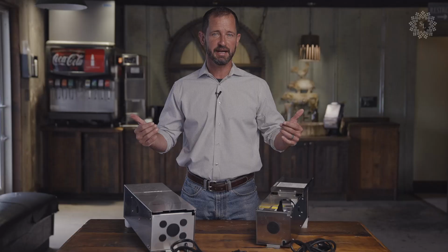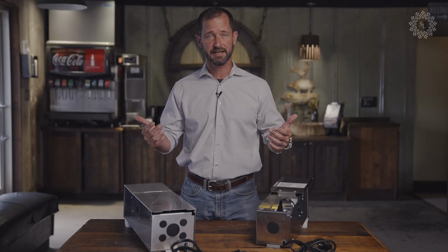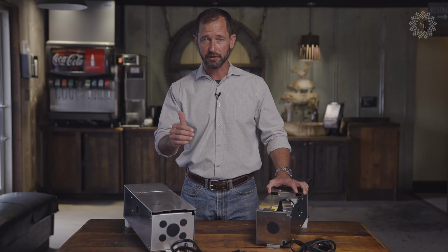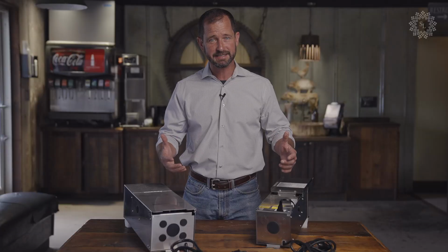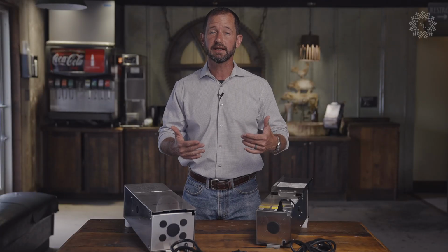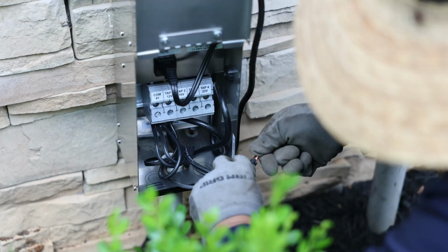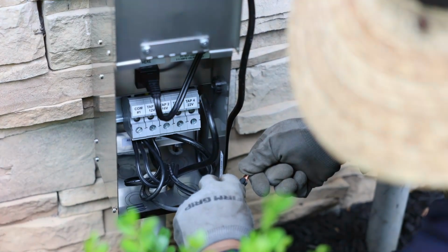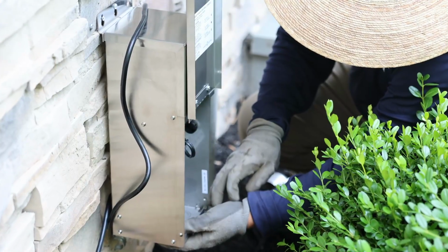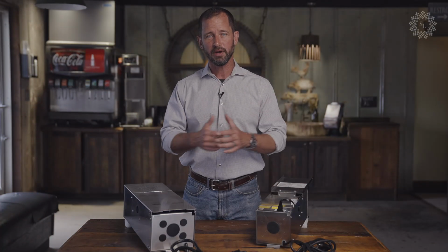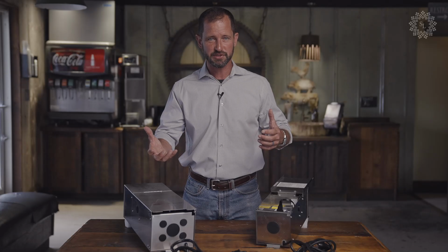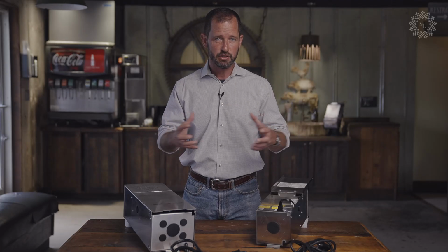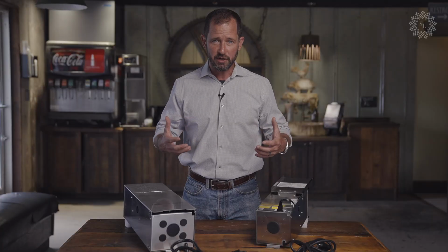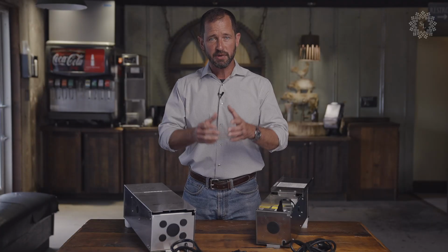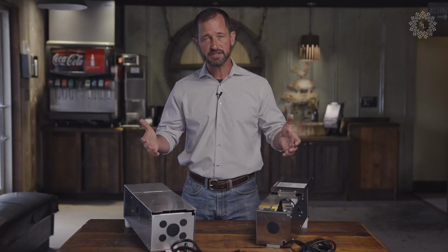As we all know, time is money on installations, and labor costs will kill your profits on any job. We design these transformers for ease of installation for professionals. They're not designed for the DIY crowd. They're more complicated, but if you take the necessary steps to check your voltage at the luminaires, check your amperage on the secondary side, and install this properly 12 inches high, you'll have an ultra reliable system coupled with Sterling lighting luminaires. These two products brought together have allowed me to grow my business, and will help you grow yours, because you can install a lighting system and know it's going to work.